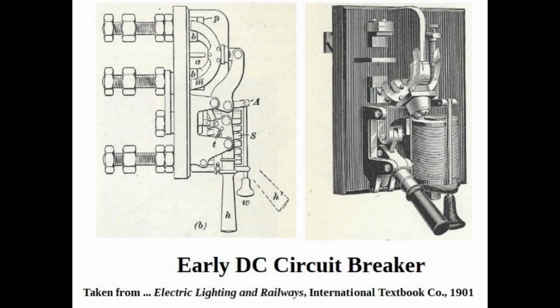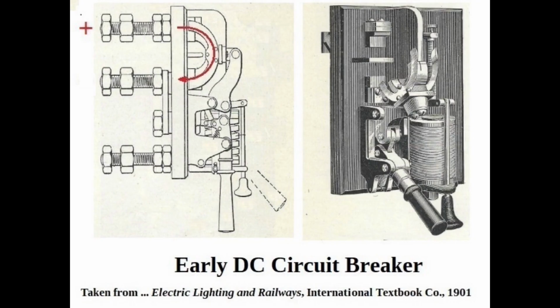We'll have a look at how one operated. On the right is a drawing of the breaker, and on the left we see the detail of the parts. The current taken by the load flowed into the positive terminal, through the circuit breaker contacts, and out of the negative terminal. A solenoid is used to detect current flow through the breaker. How it is connected to sense the current flowing in the breaker depends on the actual breaker involved. As the current in the power circuit increases, the coil unlatches the breaker and opens it. This would generally be assisted by the use of a magnetic blowout that extended the arc and quenched it.